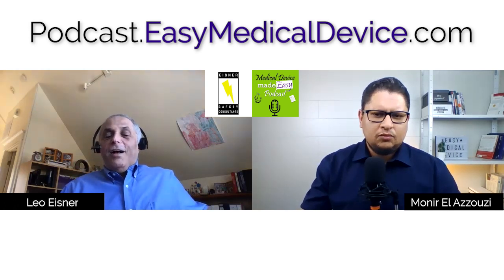Well, I think any medical device company that's an electrical medical device will have tests under the standard. So it doesn't matter if it's a small piece of equipment or a big piece of equipment. A bigger piece of equipment like a gamma camera or an X-ray is probably going to have more tests involved because of the additional mechanical testing, electrical testing, and the complexity of the device. But also, if you have additional particular standards involved, there's some products that have 5, 6, 7, 8 particular standards. You're going to have additional tests because you have all these additional particular standards involved.